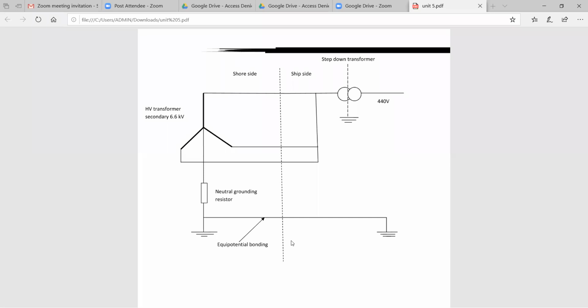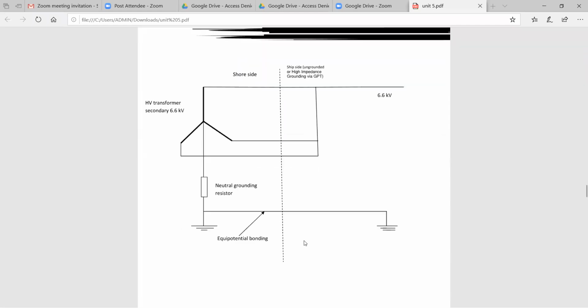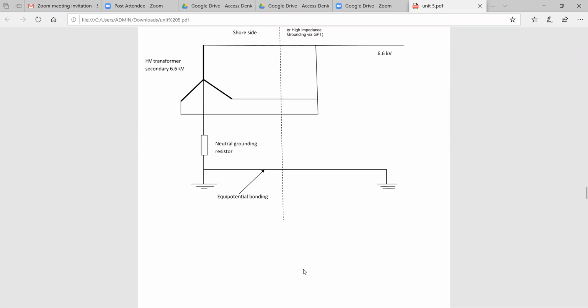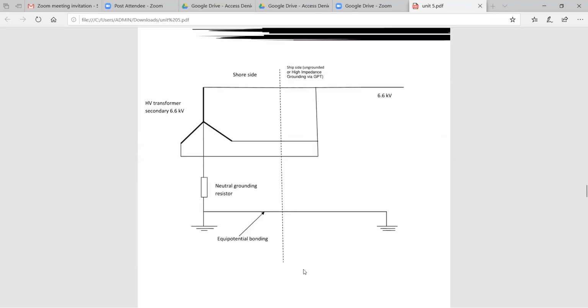Definitely, here you have a neutral grounding resistor. The neutral grounding resistor will be connected to the ground circuit, so any unwanted current flowing through the circuit will be eliminated. The second purpose of the neutral grounding resistor is equipotential bonding. Equipotential bonding means the neutral grounding resistor is connected from the shore side to the ship side, ship side as well as shore side.